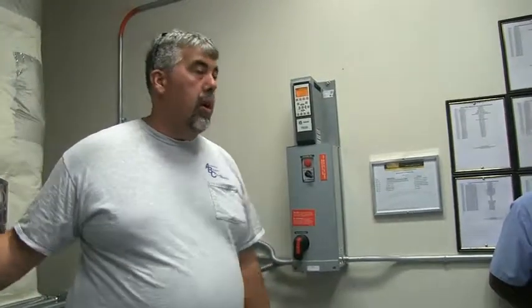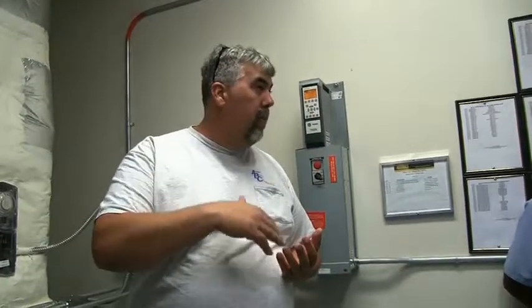And why I mentioned the other one, it looks like this, but it operates like a VAV. Based on temperature, it ramps up and down. And it also uses that same ramp up and down for heating, which will have a minimum, so it won't go so low, but it will allow it to go higher and lower based on temperature. I don't think there's anything else special. They have the electric duct heaters, which these do not have. Because it's a VAV system, the VAVs do all the heating. This has no heating involved. Okay. Now the set points allow us to go between 54 and 58.